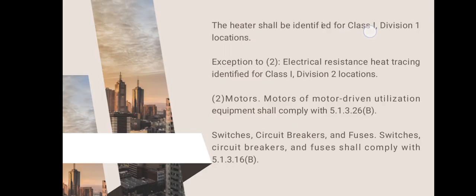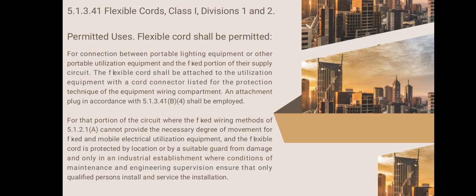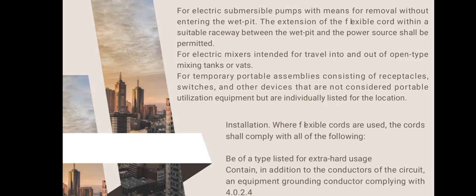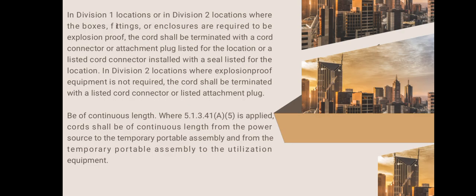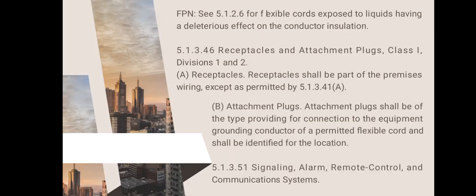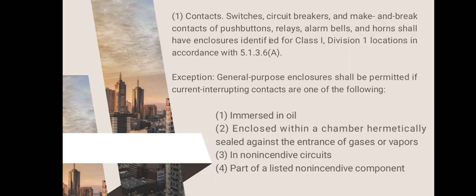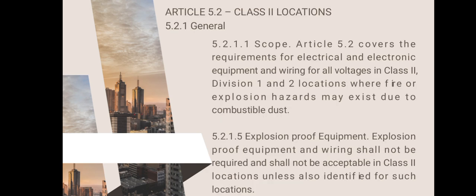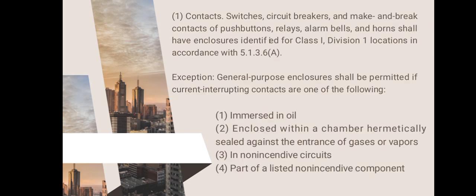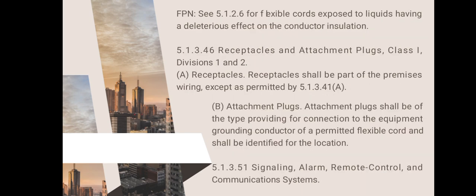And flexible cords are permitted for portable lighting and utilization equipment and where fixed wiring methods are insufficient. They must be extra hard usage type with an equipment grounding conductor. Specific termination requirements apply, including the use of listed cord connectors. Next, let's move on to receptacles and attachment plugs. Attachment plugs must provide connection to the equipment grounding conductor and be identified for the location.